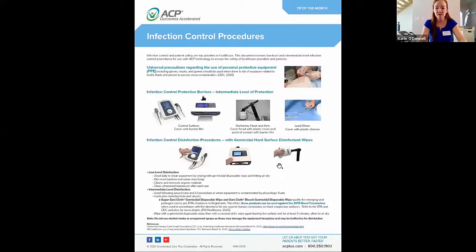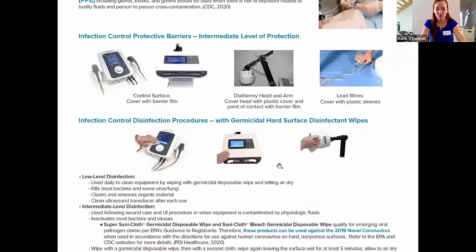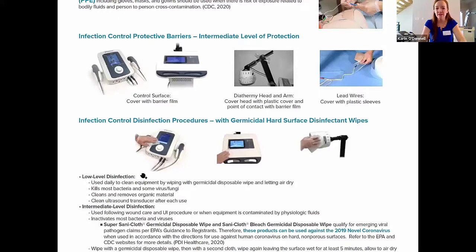I'm going to get started by sharing my screen to review some ACP documents. This is the most recent tip of the month reviewing infection control procedures. I want to first go over the two different types or levels of disinfection. One is low-level disinfection, used daily to clean equipment by wiping with germicidal disposable wipes and letting the equipment air dry. It kills most bacteria and some virus and fungi, and cleans and removes organic material.